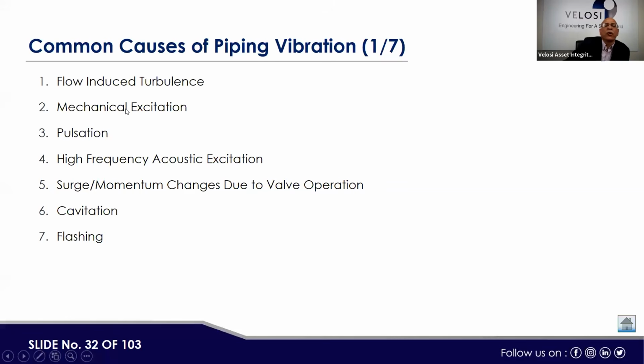Mechanical excitation goes with the pumps and compressors. Pulsation goes with the reciprocating machines and their downstream piping. Acoustic excitation occurs if high velocity is coming. Surge basically comes near the check valve, but this is a once-in-a-while scenario, when the downstream outlet is closed or there is some sudden closing of the valve. Cavitation is mostly in the pumps area, and flashing in the steam and condensate area.